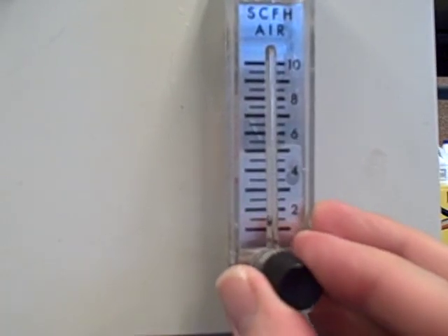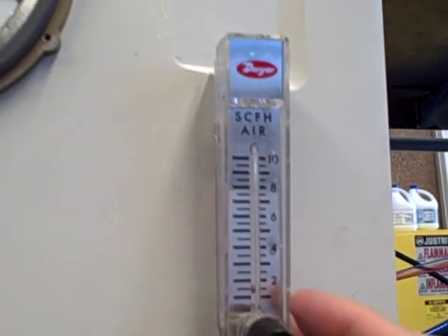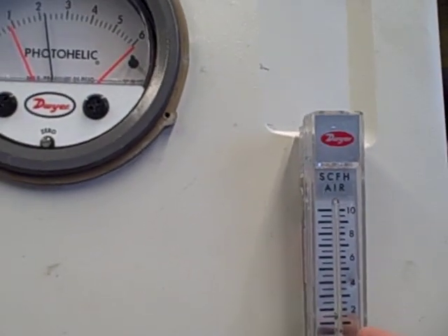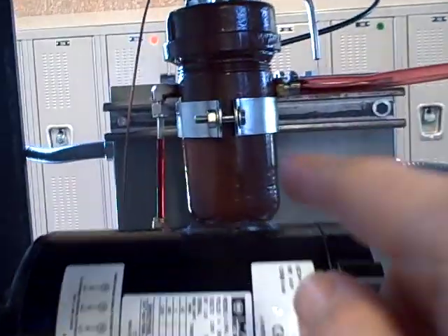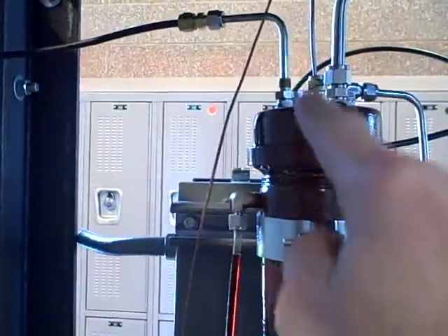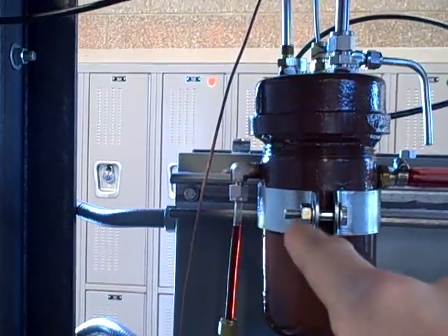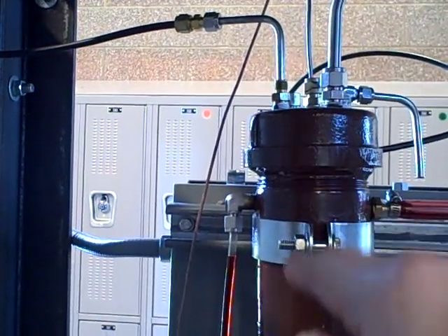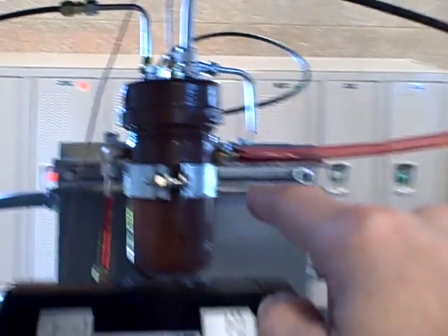This particular installation we're using the flow meter for is metering airflow into a bubble tube to measure the level of oil inside of a reservoir. There's our oil reservoir right here. It's lubricating oil for our turbo compressor system, and we have a bubble tube going into it. There's bubbling air through it.